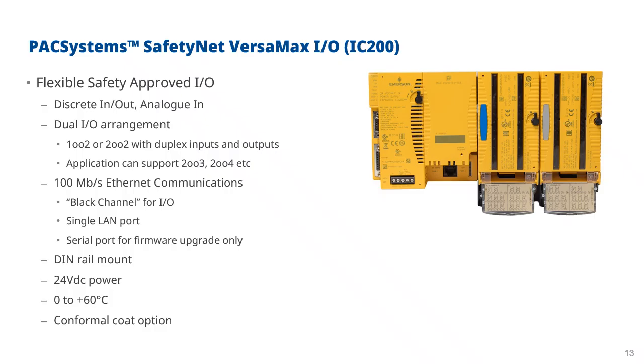And then there is voting available. Depending on what the functional safety assessment says, you can either do 1 out of 2 or 2 out of 2 based on what the requirements of the application needs. And potentially within the application, you can do additional voting. So we do support 2 out of 3, 2 out of 4, and potentially more voting solutions as well. But 2 out of 3 and 2 out of 4, I haven't come across anything that needs more than that. But generally, again, for SIL 2 applications, normally the risk mitigation doesn't need to be that high. So typically it's 1 out of 2.